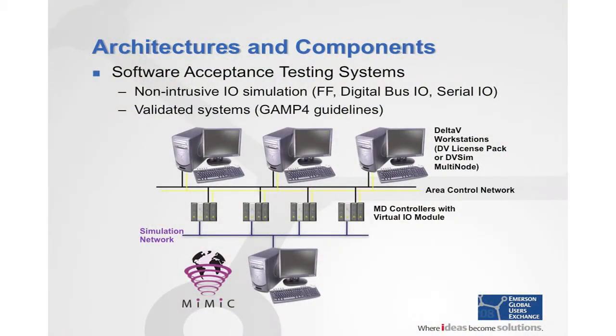For software acceptance testing, the best route to test your control system and minimize risk when moving from application software to the online environment is to use real controllers with a module called the virtual I/O module. In the drawing, you can see your Delta V workstations, your Delta V area control network, and then the MD controllers. Instead of having I/O associated with them, they have the virtual I/O module, which emulates the I/O cards of the Delta V controller — all 64 I/O cards currently available for Delta V are fully emulated, not just simulated, by this card.